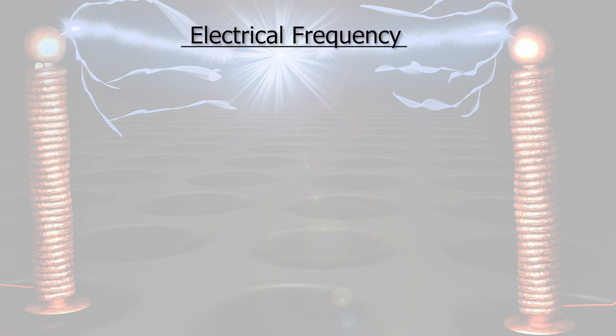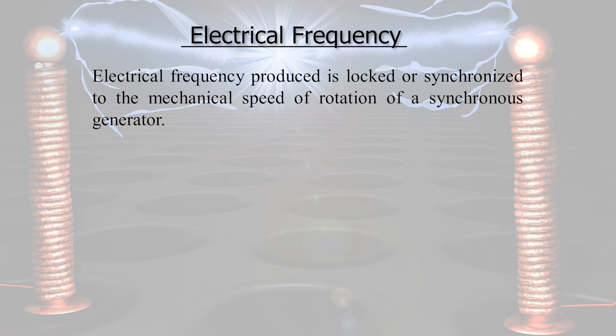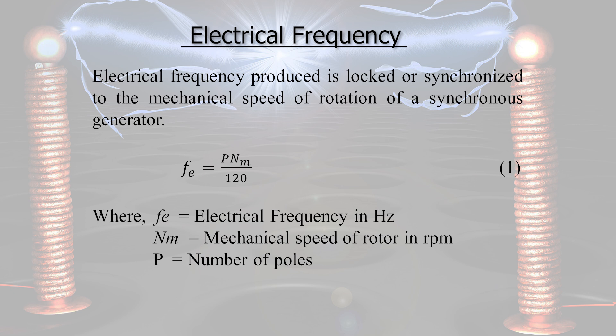Electrical frequency: the electrical frequency produced is synchronized to the mechanical speed of rotation of the synchronous generator. Nm is the mechanical speed of rotor in RPM, and FE is the electrical frequency in hertz. FE is directly proportional to Nm, the rotor speed. P is the number of poles. The frequency is linked or synchronized with the speed of the rotor — that is why the name is given as synchronous machines.